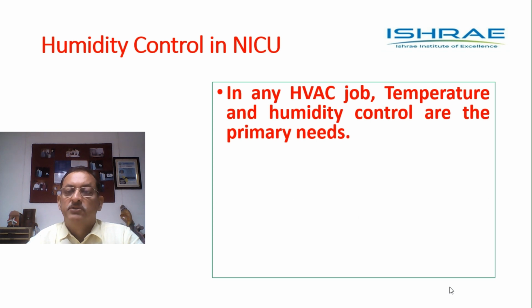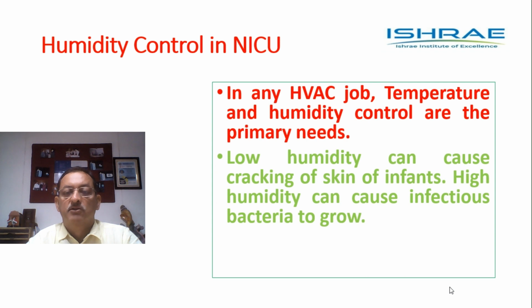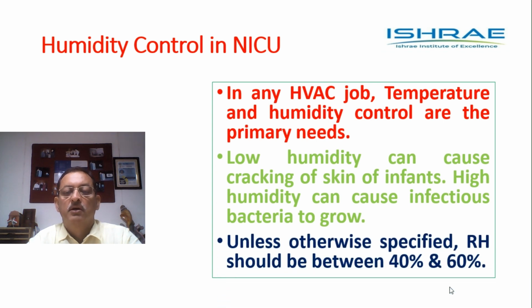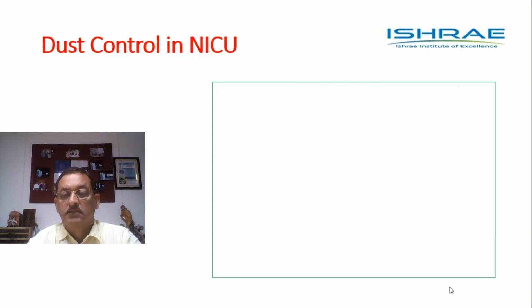In any HVAC job, temperature and humidity controls are the primary needs. Low humidity can cause cracking of the skin of infants. High humidity can cause infectious bacteria to grow. Therefore, unless otherwise specified, RH should be kept between 40% and 60%. In winter, it might be difficult to keep the RH at 40%, but care has to be taken that it is maintained, and for this purpose, water vapor could be injected.